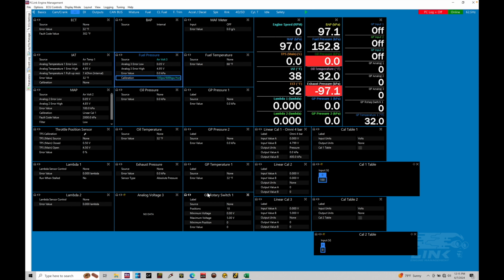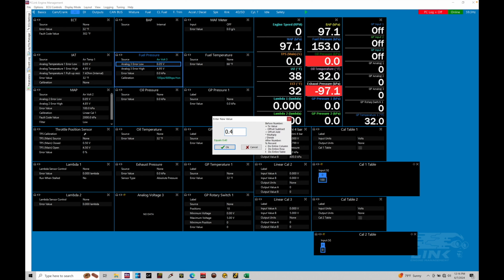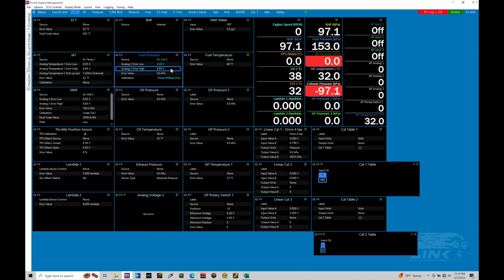So pretty simple there. That's what this calibration scale is already taking into account. At 0.5 volt, it's 0 psi, and at 4.5 volt, it's 100 psi. So that's the scaling we're working with here. Knowing that, I would set my low voltage here, saying that 0.5 volt is the lowest that the sensor can output. I'm going to set that slightly below that minimum, at 0.4. And then I know that 4.5 is the maximum voltage output for my sensor. I'll set this a little bit higher at 4.6.